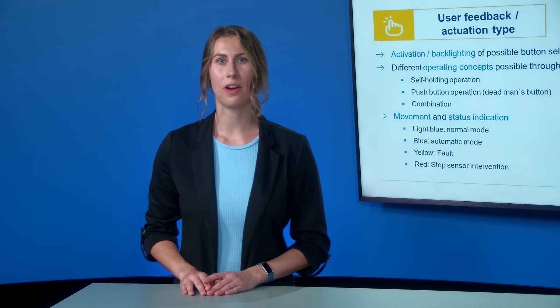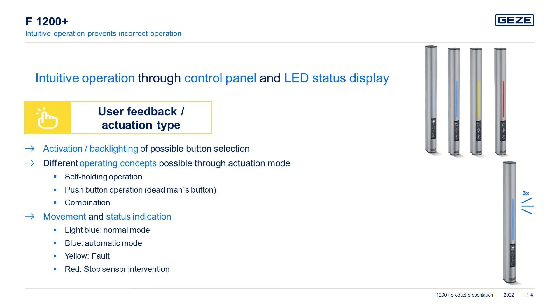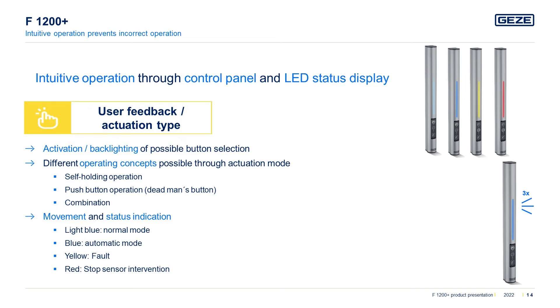Depending on the desired operating concept and security requirements, different operating modes can be selected for the three buttons. With a self-retaining operating mode, the drive is brought to the desired end position by pressing a button once. With push-button operation, also called dead man's button, the button must be held permanently until the desired end position is reached — releasing the button stops the drive. A combination of push-button and self-retaining modes allows automatic switching of operation.